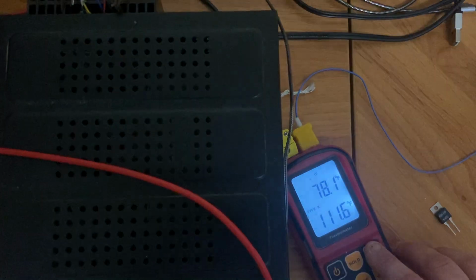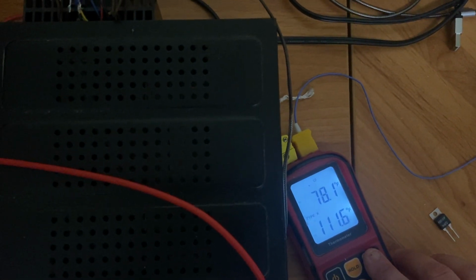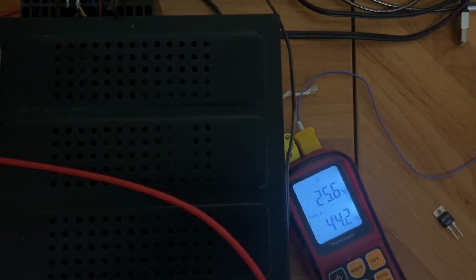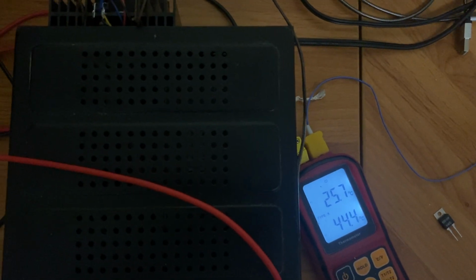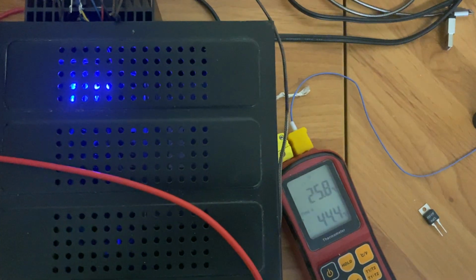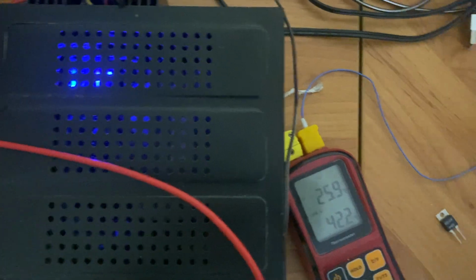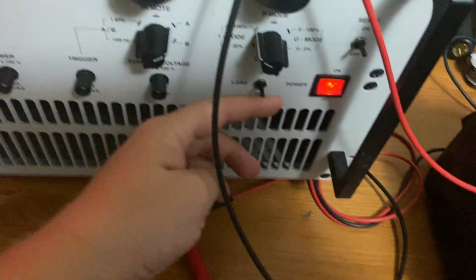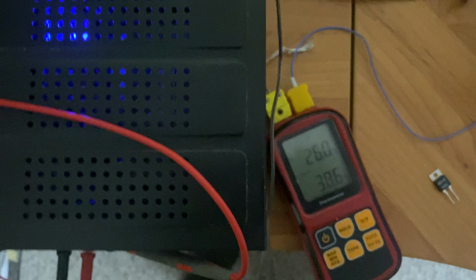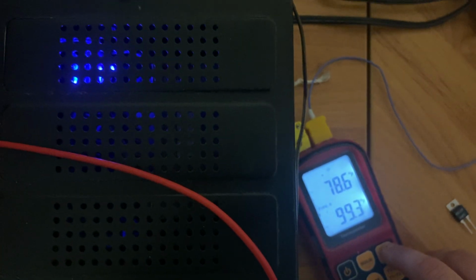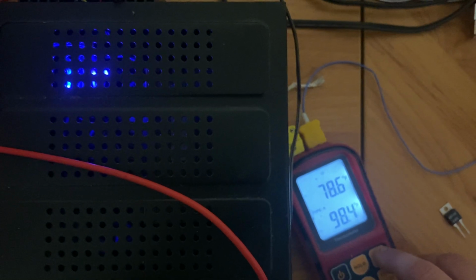So we're at 44 degrees Celsius, which is 111.6 degrees. Again, switch is rated for 45. There it goes. It kicked on at 44 and a half, or just under. I'm going to shut the load off. And as you can see, the fan is running. So now we'll just see when it kicks back out. We're already under our 100 degrees Fahrenheit.